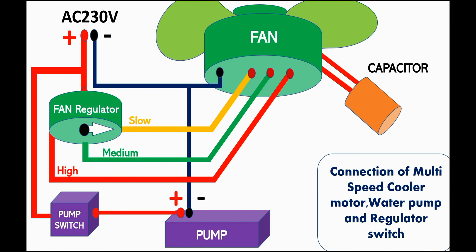If it shows any mismatches in rotation, then interchange the connection of phase terminal from the regulator switch. It is the connection in between 3-speed cooler motor, water pump and regulator switches.